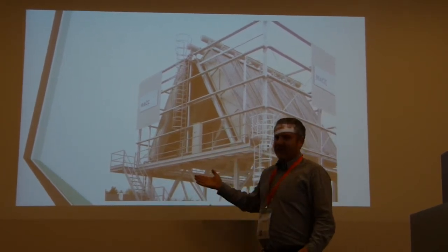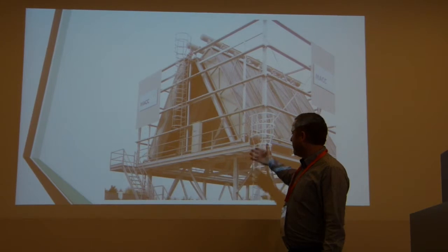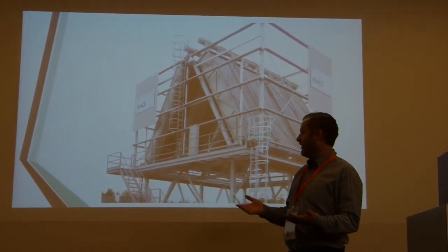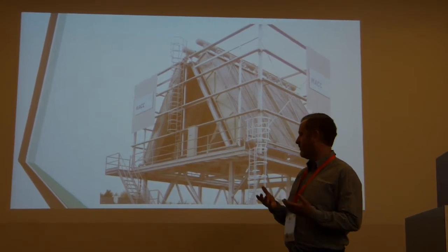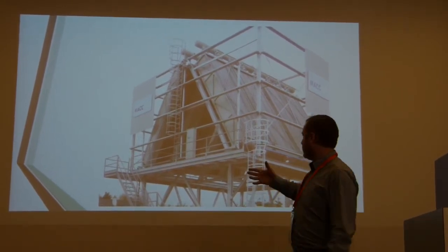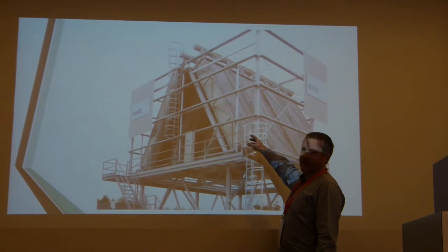This is in contrast to what's there conventionally, because conventionally you just have this 10-metre fan, you turn it on in the morning and it does its job, but there's no intelligence around what speed it should be running, and there's also, say, areas of the heat exchanger that aren't working, whereas in this scenario, because of the proximity of fans, everything's working.